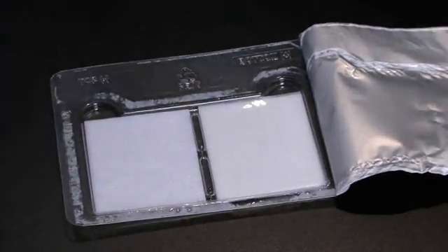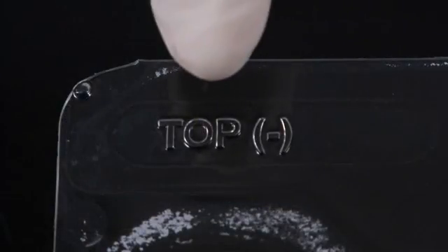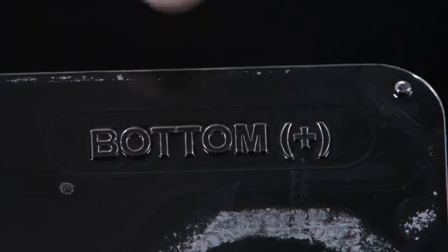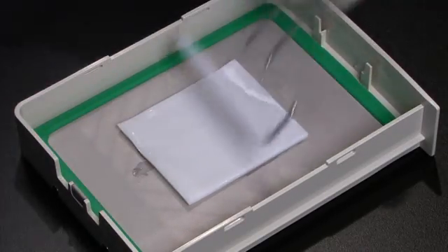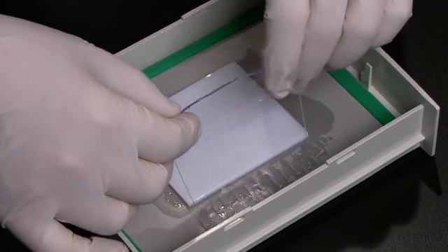The mini transfer pack tray contains two ion reservoir stacks located side by side. Each stack can be identified by the labeling on the tray. The bottom stack contains the membrane and is placed in the bottom of the cassette with the membrane facing up. Roll the stack and membrane gently with the blot roller to remove any air trapped between the stack and the cassette.